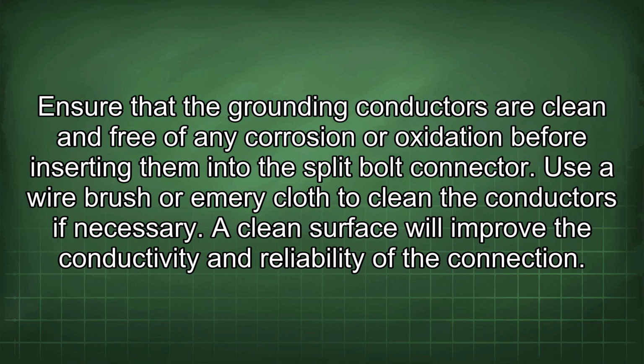Ensure that the grounding conductors are clean and free of any corrosion or oxidation before inserting them into the split bolt connector. Use a wire brush or emery cloth to clean the conductors if necessary. A clean surface will improve the conductivity and reliability of the connection.